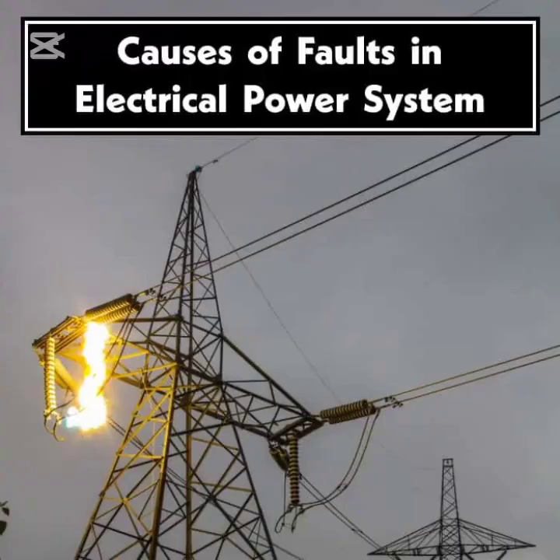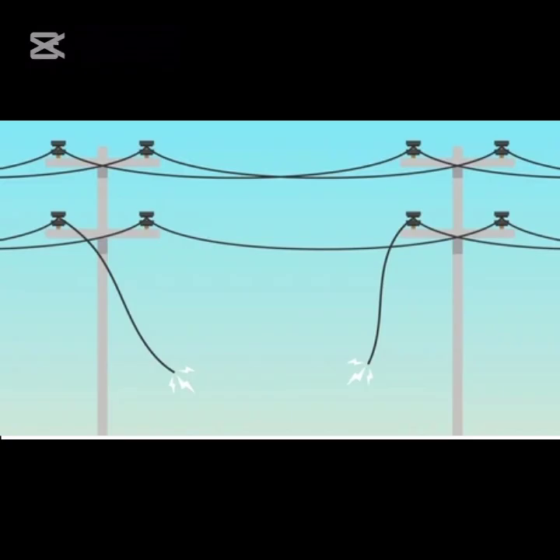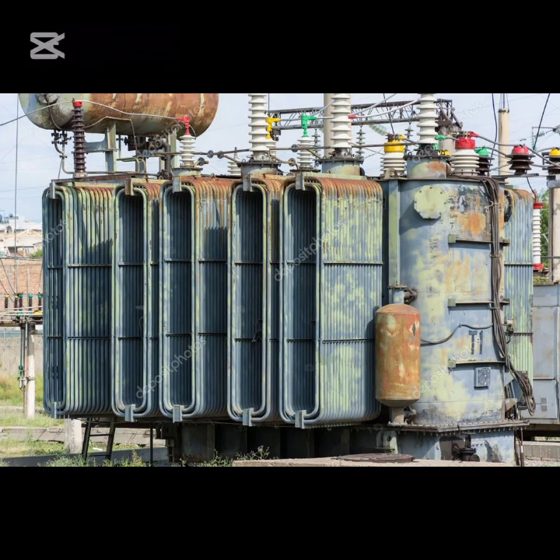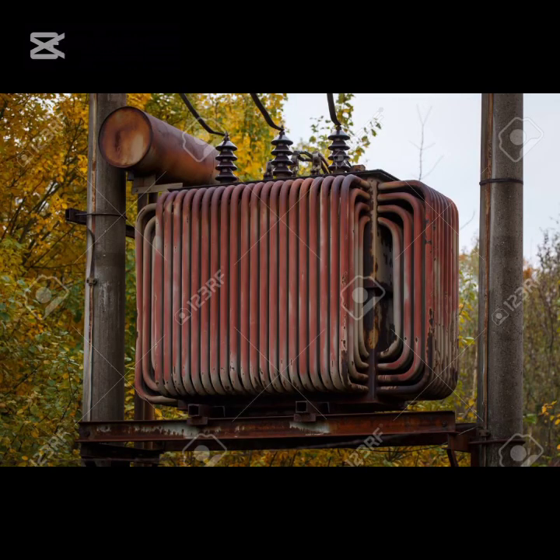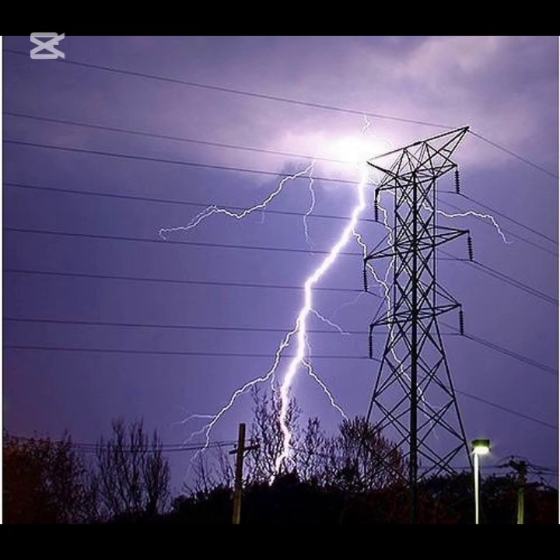Now that we have covered short circuit, let us examine the causes of short circuits in power systems. A short circuit in a power system arises from abnormal conditions, which may result from either internal or external causes. Internal causes include equipment or line failures due to insulation breakdown in generators, transformers, or other components. These issues can come from aging, poor design, or improper installation. External causes involve insulation failure triggered by lightning, overheating due to overloading, or physical damage, such as vandalism or accidents.